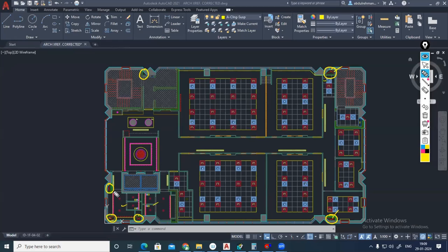Normally, when we are placing our machine, if it is possible, you have to place your machine very near to the chilled water route. From here, I will have the main chilled water pipe, supply and return. Then I'll take it to the lobby, then through the corridor only I'll take my pipe. If I place my machine here, another machine here, and the next one here, the length between the chilled water supply and return pipe to the main connection will be minimum. So the installation cost we can decrease there.